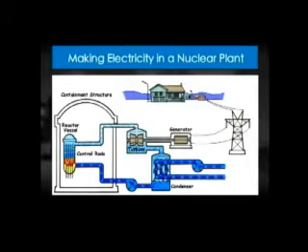So when you hear about a power plant having a condenser leak, that's river water that leaks into the condenser. The pressures are such that the river water goes into the reactor. It doesn't go the other way. When Vermont Yankee or another plant springs a condenser leak, it's dirty river water going into the nuclear reactor, not radioactive water going out into the river. There's other leaks that pollute the river, but the condenser leaks that have been endemic to Vermont Yankee are designed so it leaks in, not out. And then the cycle begins again.